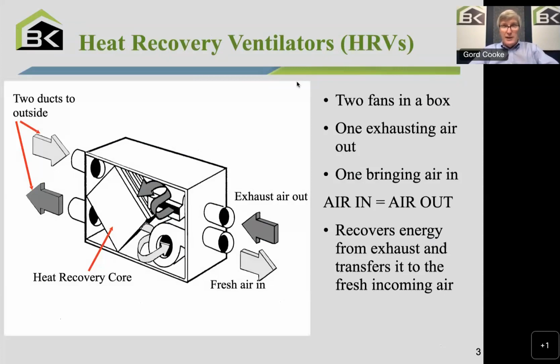Now, it's okay if people say, I don't want to run it in the summer because my windows are open. That's totally fine. But in times where windows are closed for extended periods of time, then we would say the occupants need fresh air. And that's what this device is doing. And the nice part is, unlike opening a window where you have to pay for 100% of the energy cost of heating up, these devices are roughly 70 to 80% efficient. That is, they recover 70 to 80% of the temperature difference between the inside air and the outside air.